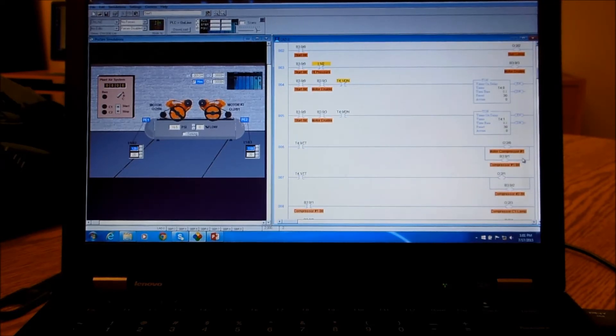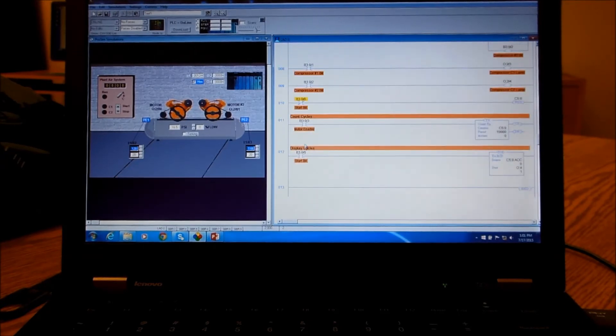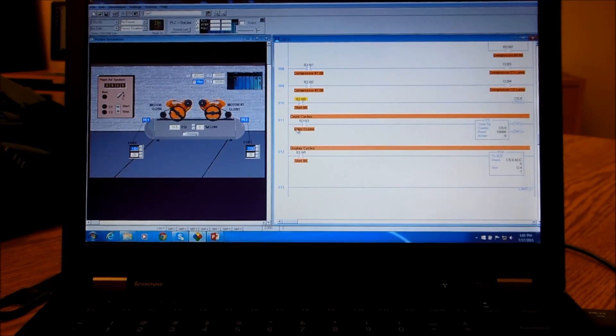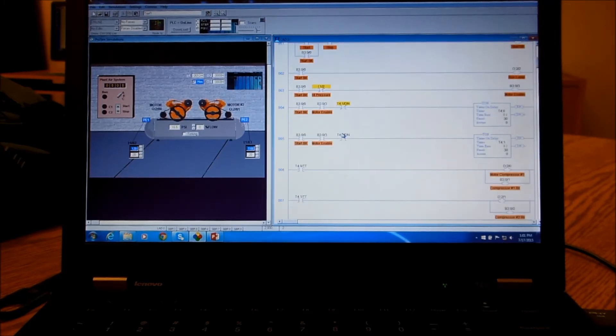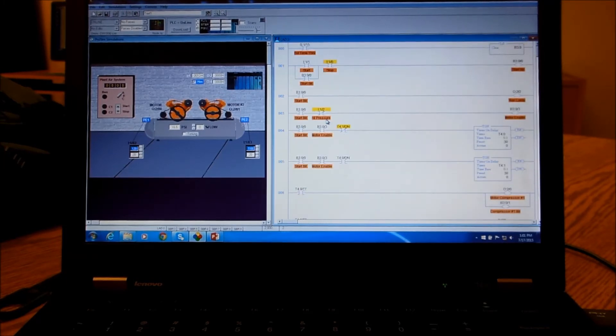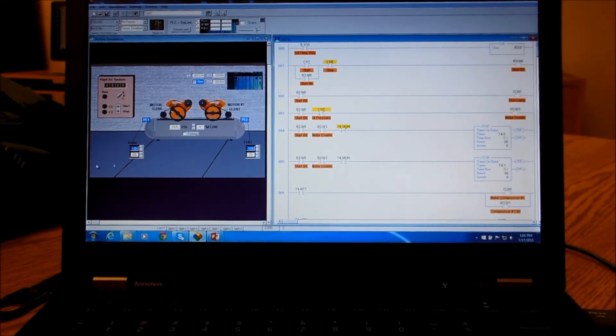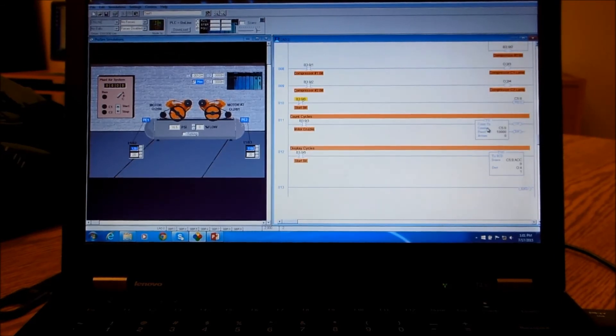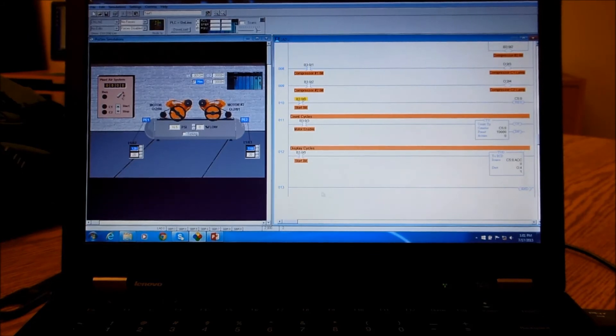The bits internal for the compressors control the lamps. Down here we have the count cycles, and this is with the motor enable signal. Again, the motor enable signal toggles off when we hit the high pressure and then we get down to low pressure it toggles on again—so that's what counts. Then we display the cycle counters, how many times we go through the full cycle over here. This is just a binary to BCD or seven-segment type counter and that'll make the display over here work.